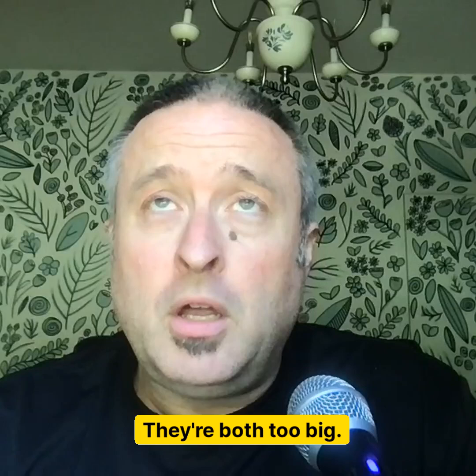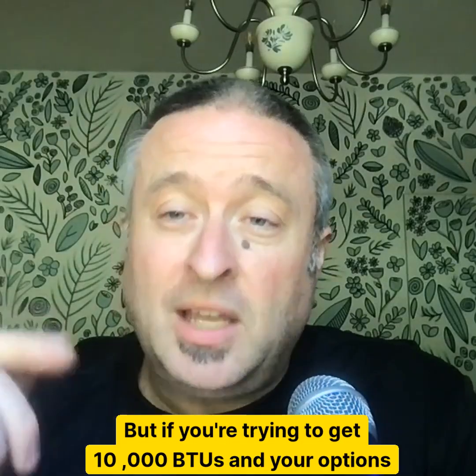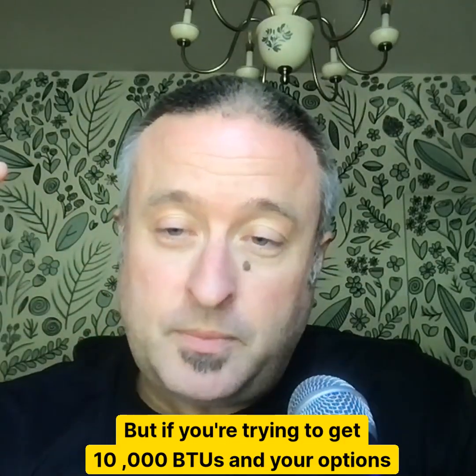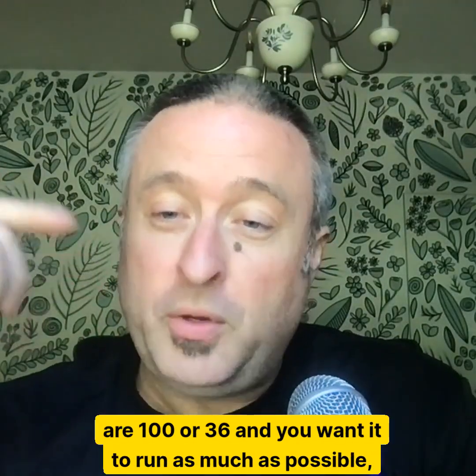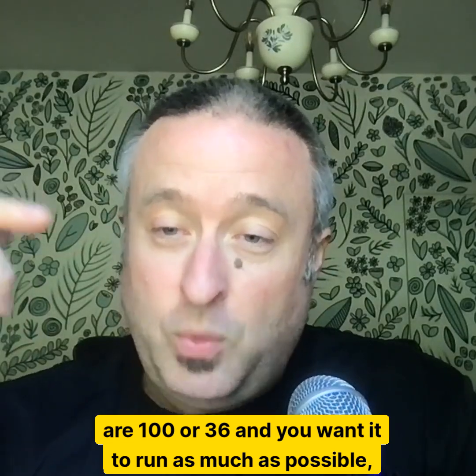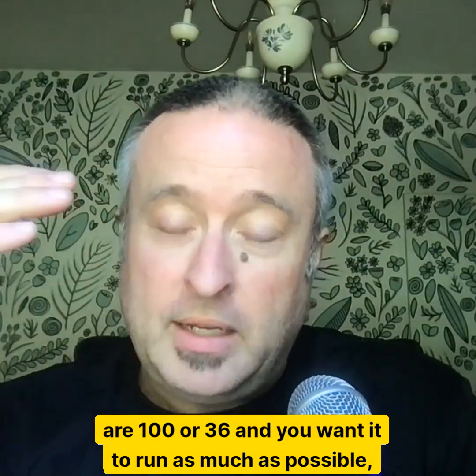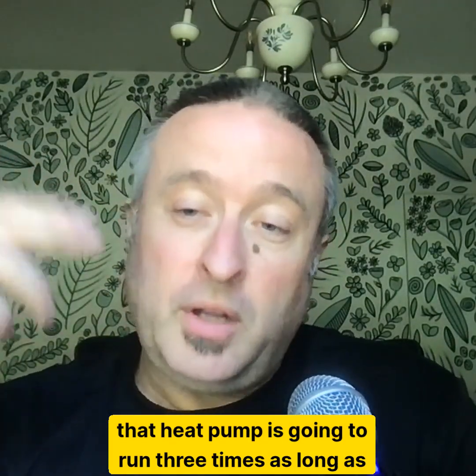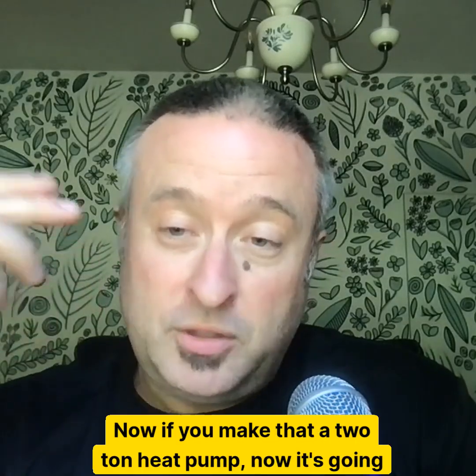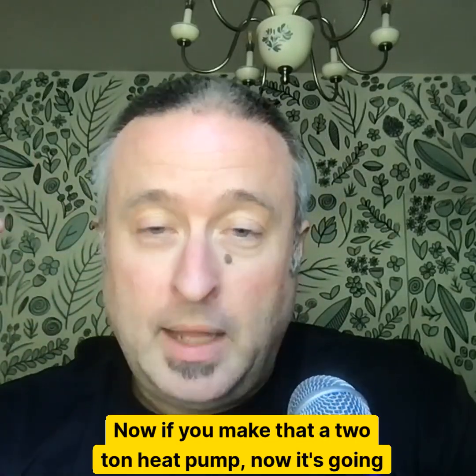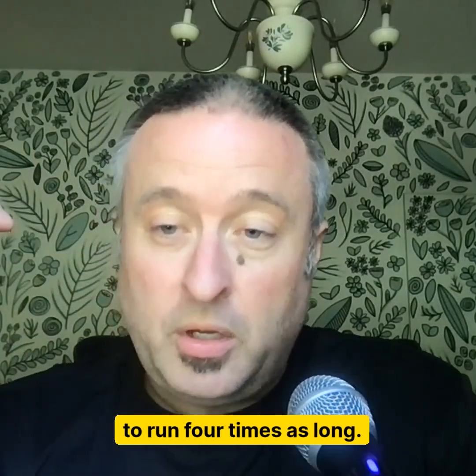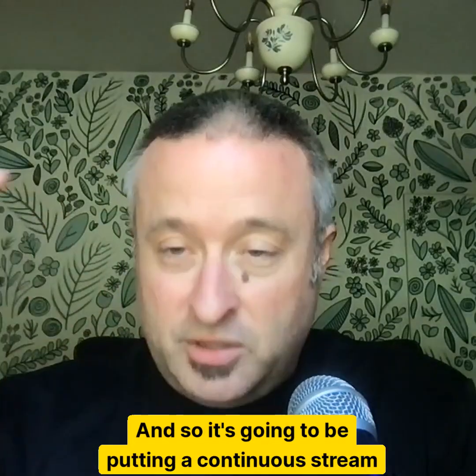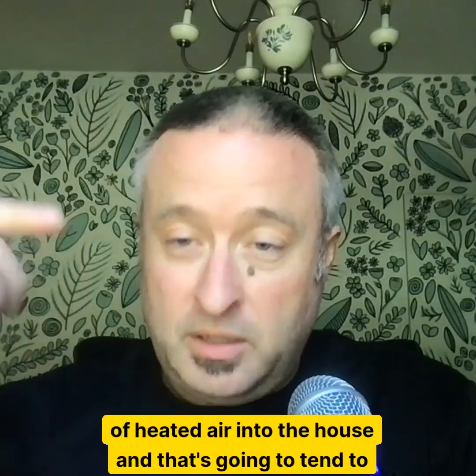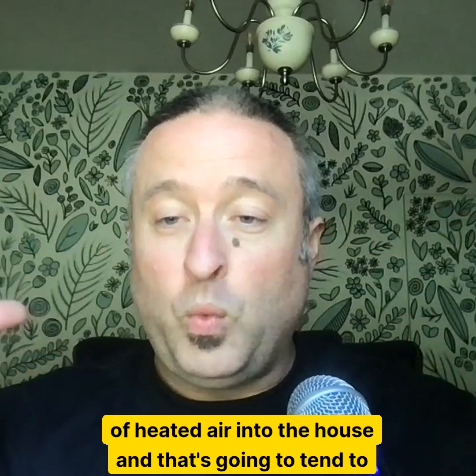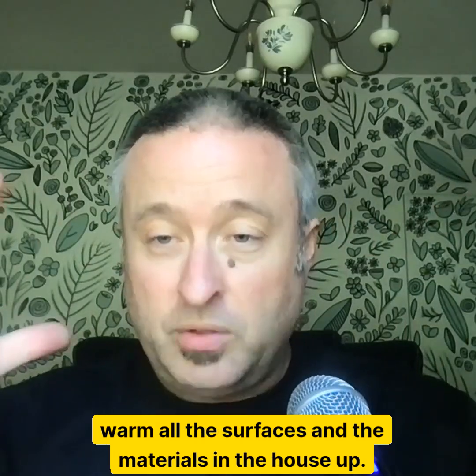They're both too big. But if you're trying to get 10,000 BTUs and your options are 100 or 36, and you want it to run as much as possible, that heat pump's going to run 3 times as long as the furnace. Now, if you make that a 2-ton heat pump, now it's going to run 4 times as long. And so it's going to be putting a continuous stream of heated air into the house, and that's going to tend to warm all the surfaces and the materials in the house up.